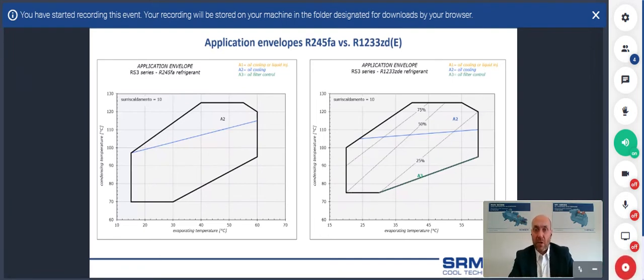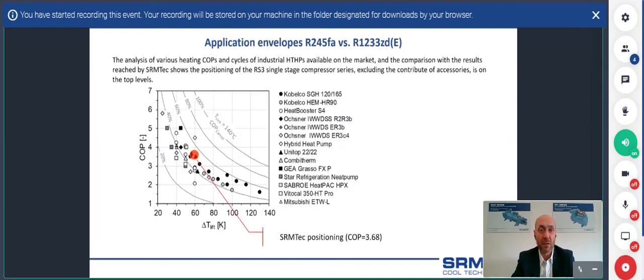So this is what is important for the compressors. But we have also made an evaluation of how we are positioned in the market in the real system. This graph shows a map of the efficiency of the heat pump system produced by different manufacturers. Of course, on the x-axis we have the temperature lift, and on the y-axis the efficiency of the system. The COP decreases with increasing temperature lift, as we have already seen before.